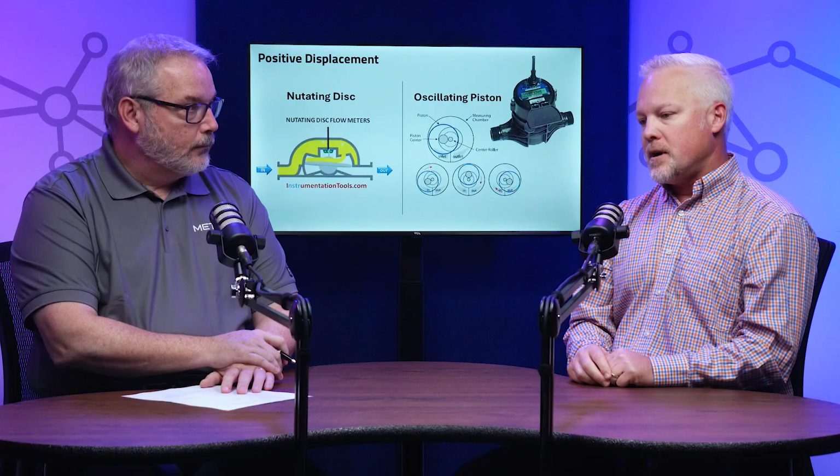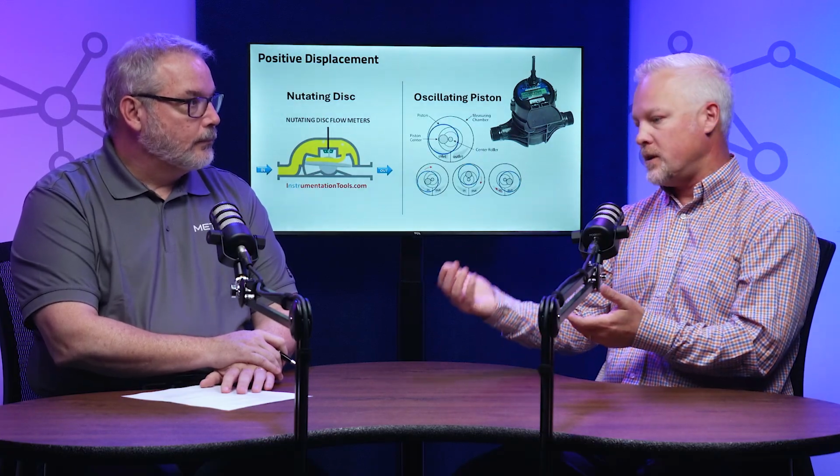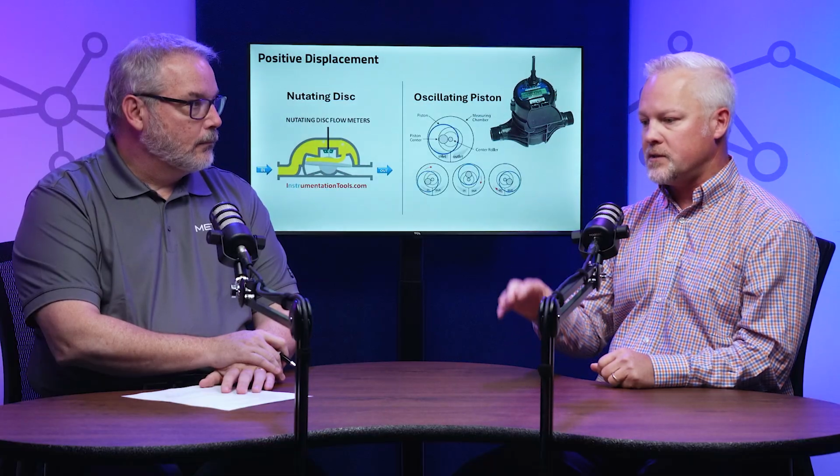Okay, great. Is there any orientation restrictions on that one? No orientation restrictions. I would say maybe some of the drawbacks to PD is they can be noisy. So like if they were installed in somebody's basement, like in the northeastern part of the United States, that echo through the copper pipes is probably not something that a lot of people would be a big fan of. And then obviously there's a lot going on in the mechanical action, so they can tend to wear maybe a little bit earlier than some of the other types.